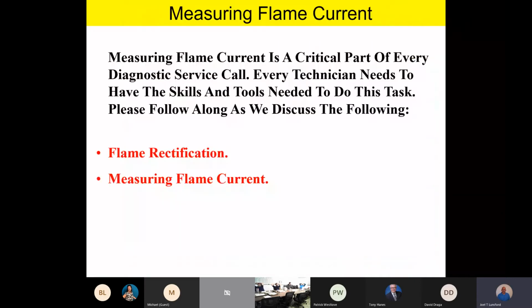Well, fantastic. Team, at this time we're going to talk a little bit about measuring flame current. I'm going to make it a point to go over measuring flame current on each one of our furnace overviews, because I think this is really important. Technicians need to be able to do this, and I recommend that every time you make a furnace service call, you check that flame current, because the flame sensor can get dirty. If you're going to clean the flame sensor, we recommend using something like Scotch-Brite.